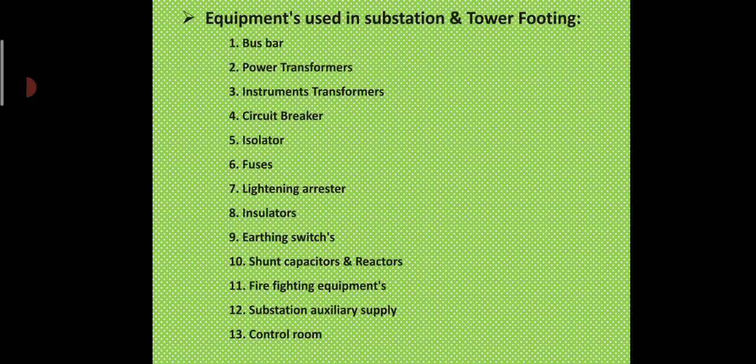In the case of transformers of large kV ratings, a single three-phase unit or three single-phase units are used. Single three-phase units are economical and occupy less space. The connections are also relatively simpler, but the single-phase units are easier to handle. They are, however, more expensive and require more space.